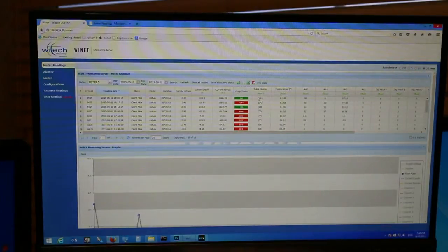And okay, pulse counter. This number here depends on the K factor. Okay, so the unit itself shows you the pulses. When you see on the display, you see the pulses, total pulses. If 1 barrel is 10 pulses, then the remote unit is going to show you 10 pulses, but here you're going to see 1, because the calculation is done here on the unit. Okay, just have that in mind. On the remote unit, you don't have a K factor. It just counts pulses and sends the information here, and that is calculated here.